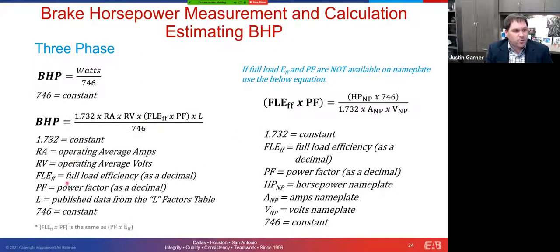It's interesting to note, though, we can measure running amps, we can measure running volts, and again, we always take the average of our measurements there. I'm going to show you how to calculate this, and I'm going to show you how to get this so that we can ultimately estimate our brake horsepower. So over here, if we need to try to figure out our full load efficiency times power factor, because that's not something you can always get off the nameplate, and certainly not the power factor. That's something you have to typically measure in the field. But you can estimate it.